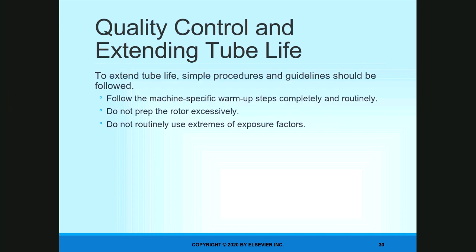Now, some other ways to extend tube life: you can follow specific warm-up steps that are set by the manufacturer of the equipment. You don't want to prep the rotor excessively. Since it's a 2-part switch, it is possible to push it down halfway and prep the rotor. Sometimes with pediatric patients, you'll do that so you can watch the baby breathe in, breathe out, and time the exposure correctly.